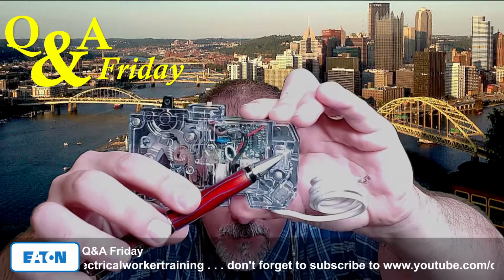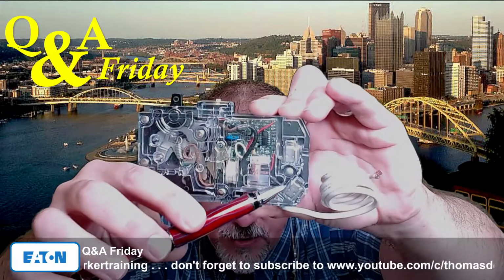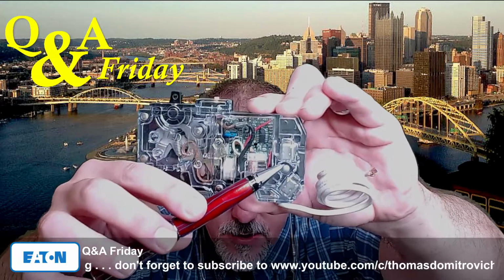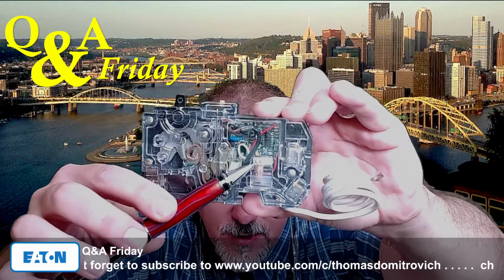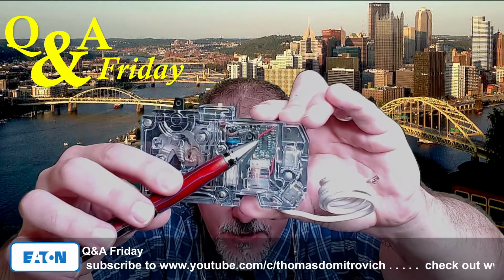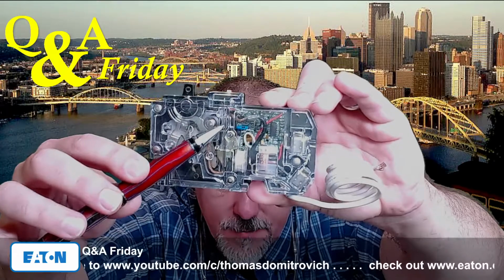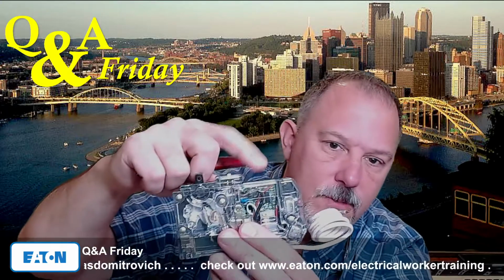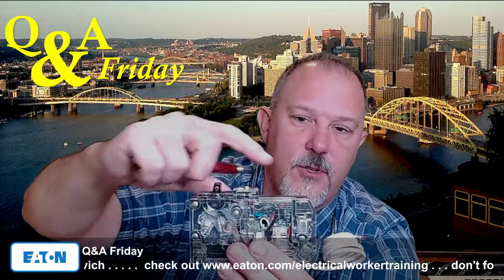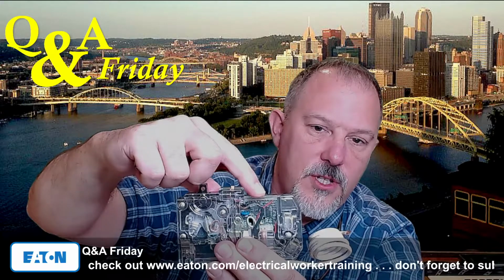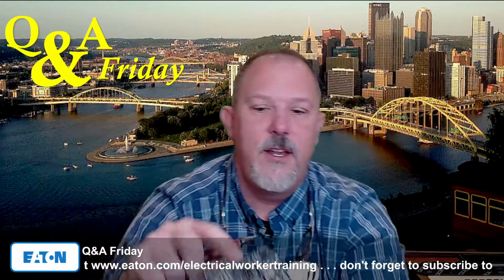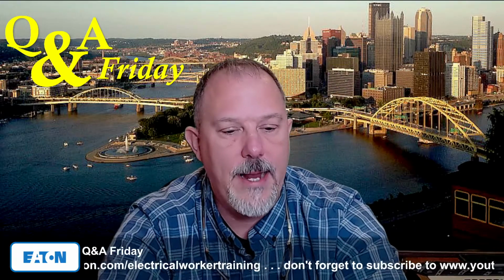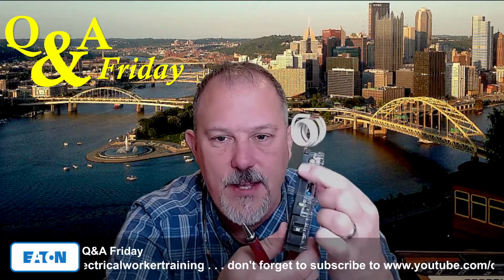So you've got my hot conductor lug, and I've got my neutral. My hot conductor comes down through this sensor. And look, this black conductor is flexible and it comes up and goes to the rest of the standard thermomagnetic circuit breaker. And look where it routes. It routes right here, there's your handle, and there's your conductor. That conductor is going to get a little warm, and where is it? It's right here on the face of this circuit breaker.